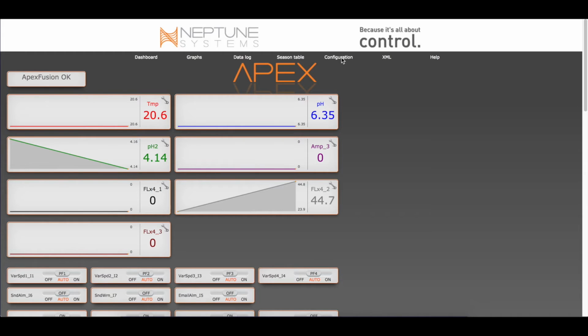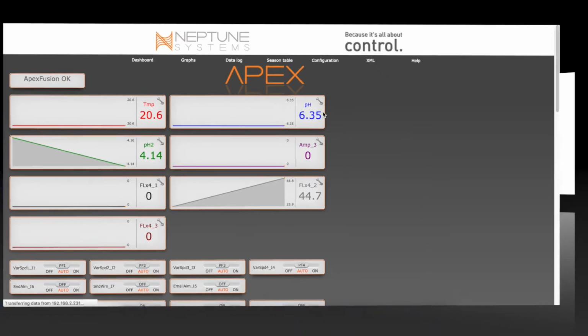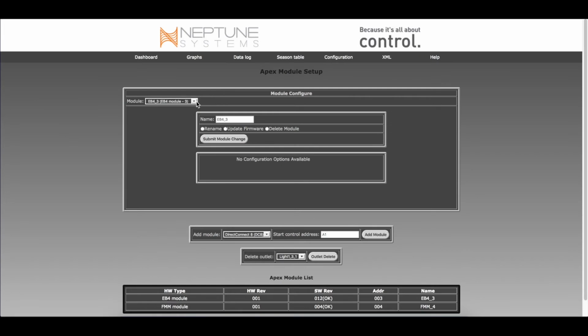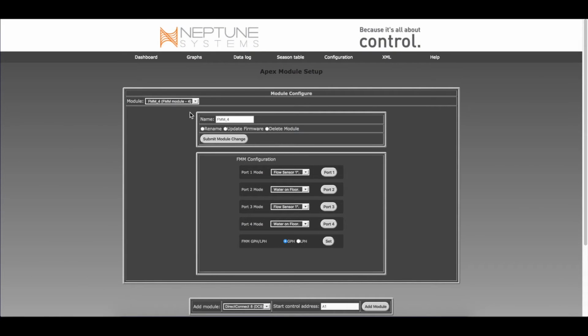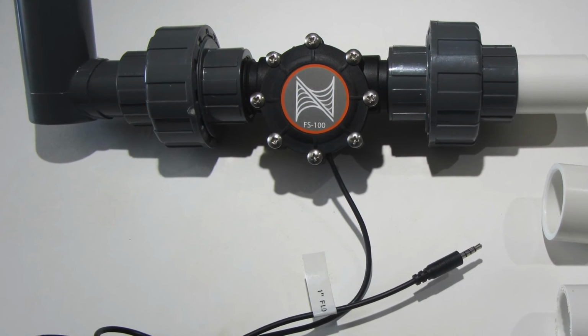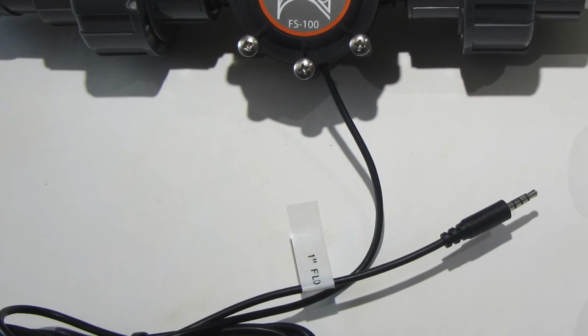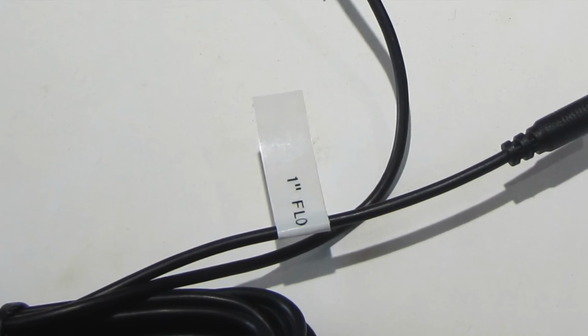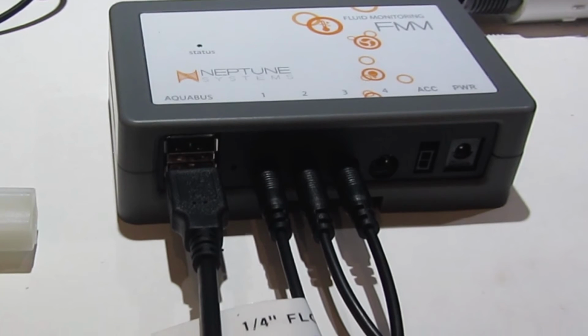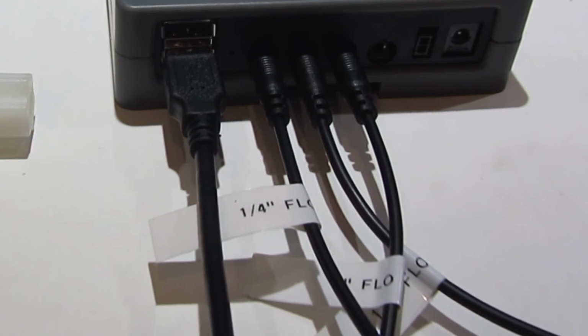In the classic dashboard, navigate to the Configuration drop-down menu. Then click on the module setup, and then in the upper left-hand corner in the drop-down menu, choose the FMM module. Now you'll need to configure each port one at a time. Note, all flow sensors default to 1 inch. If you labeled the cables like we recommended earlier, this will make this part a little easier to identify what size flow sensor you have in what port on the FMM.